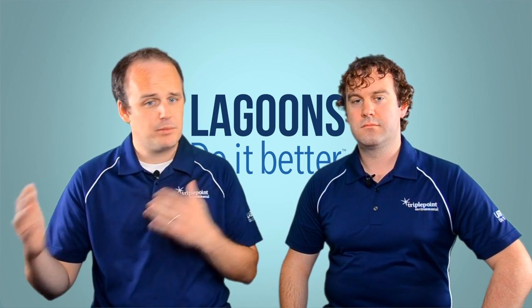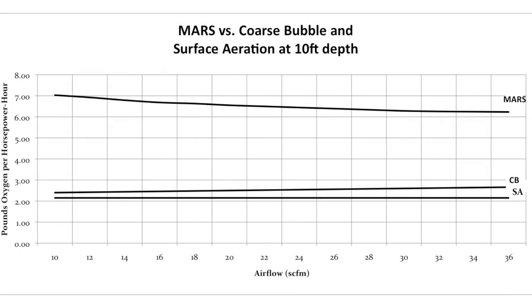When you take a step up to coarse bubble, that's sitting on the bottom, using gravity and the bubble to transfer oxygen to water from the bottom to the top. You typically see about 2 to 3 pounds of oxygen per horsepower-hour.